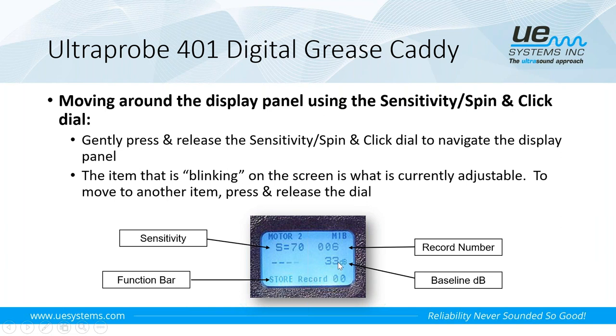The number here on the middle right is the baseline dB. Once we've created the route, we load the route into the Grease Caddy, and we go out and collect that initial round of decibel level readings. The next time we load the route in here, it's going to bring over the baseline dB. The UltraTrend DMS software that we'll talk about will default and set the first reading that you download into it as the baseline. But we can change that baseline at any time, with a simple one click of the mouse. When we load that route in here, whatever the baseline is for each one of these points, it'll bring over the baseline dB. So we're going to know at any given time along the route what the baseline dB is for each one of those points.